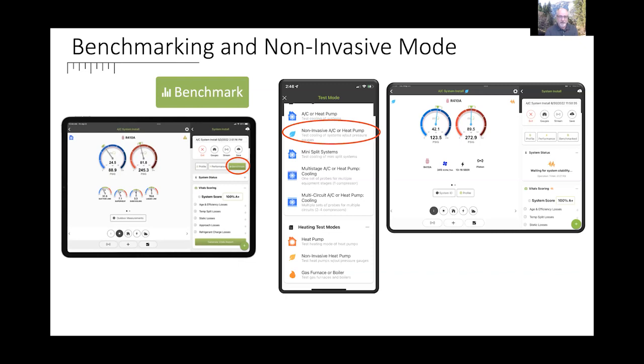Then when we come back to service this unit, I know its benchmark, meaning I don't have to tap the refrigerant charge anymore. I can just hook up the temperatures on the line set, not the actual pressure probes doing the refrigerants, and determine if it's still within compliance of the original install, in a non-invasive mode.